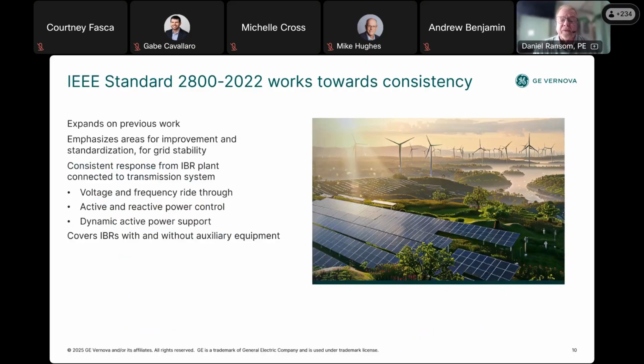IEEE Standard 2800-2022 expands on the previous work of 1547 and the grid codes and some of the early NERC codes. It emphasizes the areas for improvement and standardization in IBR plant operation. The focus is on grid stability and consistent responses from IBR controllers. The standard establishes minimum technical requirements for the interconnection and performance of the IBR plants connected to the transmission system. The standard includes specifications for voltage and frequency ride-through, active power control, reactive power control, and dynamic active power support under abnormal voltage and frequency conditions.